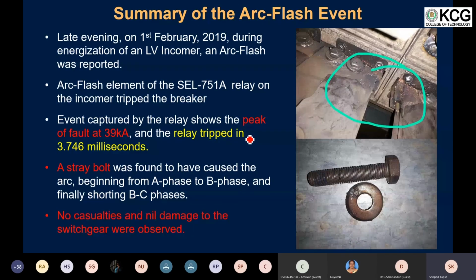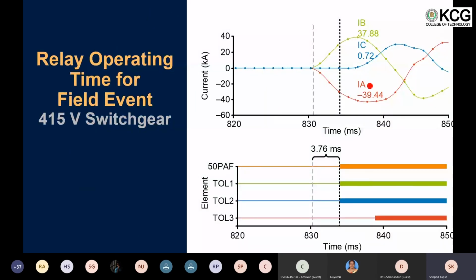We can pretty much see that from the event report which was captured from the relay. Here you can see that initially there was a peak in the current seen by the B phase and the A phase alone, and later, gradually, within a fraction of a millisecond, we can see that the third phase, the blue C phase, was also involved. At this time, the relay sensed the arc flash event and operated in just 3.76 milliseconds.